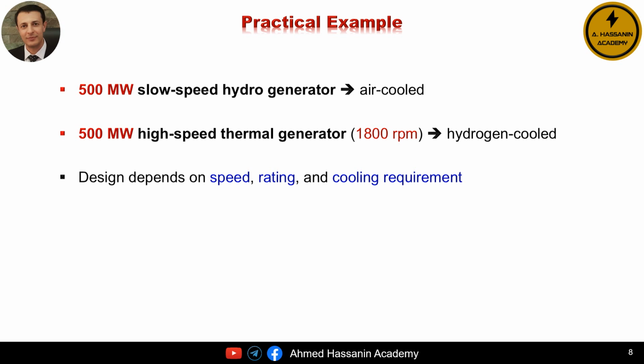Even though the power is the same, this generator is much more compact. As a result, air cooling is no longer enough, and hydrogen cooling becomes necessary to handle the higher thermal stress. So the takeaway is simple. Generator design is not based on power rating alone. Engineers must consider operating speed, machine size, and cooling requirements together to ensure safe, efficient, and reliable operation.